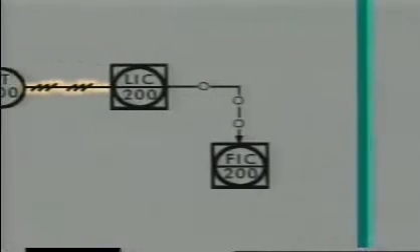Now, let's look at lines that represent connections between devices. You may already recognize this dashed line as the symbol used to represent an electric signal. But the international symbol, a solid line with triple crosshatches, is also used to indicate an electric signal.